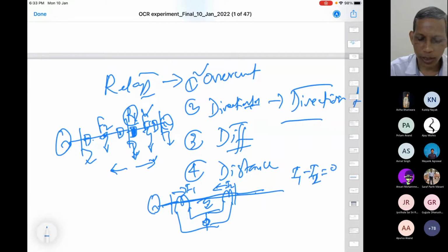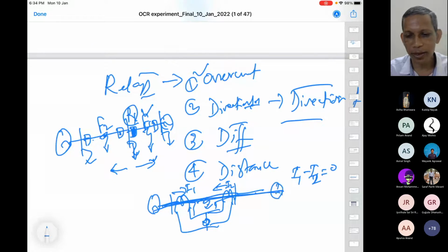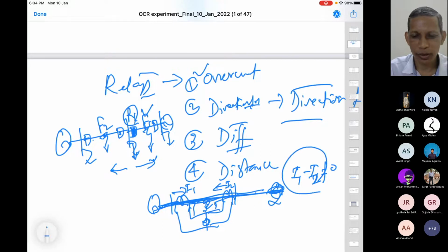But whenever an internal fault happens, the I2 current now reverses. Earlier current was flowing from left to right. If there are sources on both sides, or if it is a radial system, I1 and I2 will be no more the same, because the fault current will be substantially high and the current on this side will be much lower. So the difference of I1 and I2 will be no more 0 during an internal fault situation. So for this line or this element, whatever it may be, we can make a clear judgment of an internal fault, external fault or no fault situation in the system from this I1 minus I2, which we call the differential current.